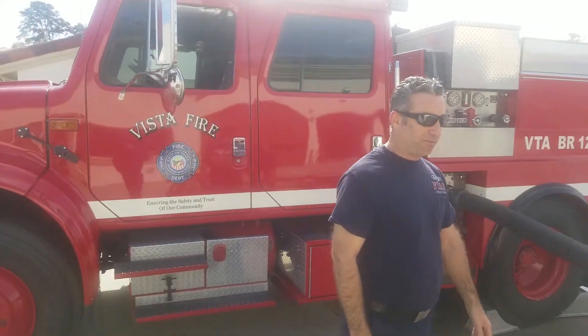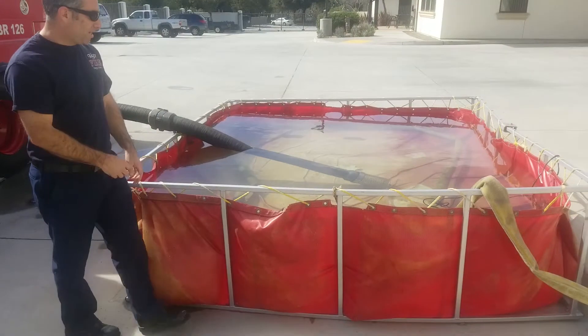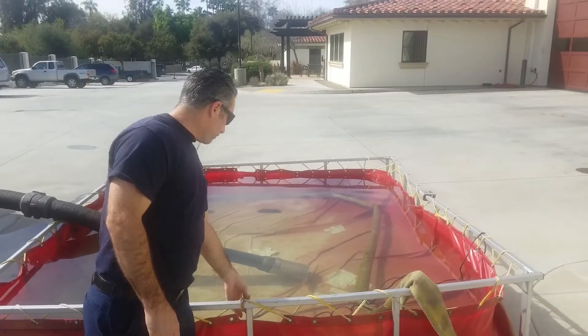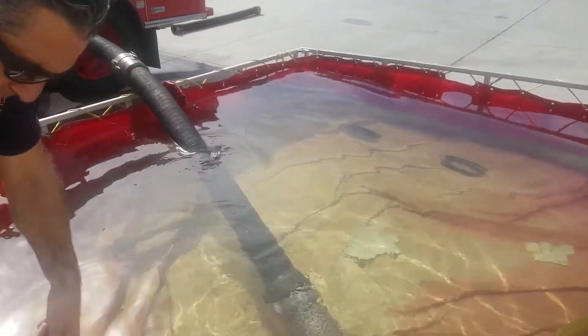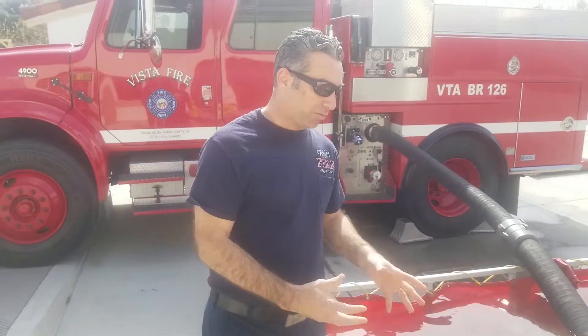This is our sump. Some things I want to look for: make sure my water is clear, make sure there's no debris floating around — it's a good site. We're gonna secure our suction line, make sure we've got a good two feet of clearance around. With that strainer, it can kind of rest near the bottom since this is a clear commercial product — nothing can get sucked up from the bottom.